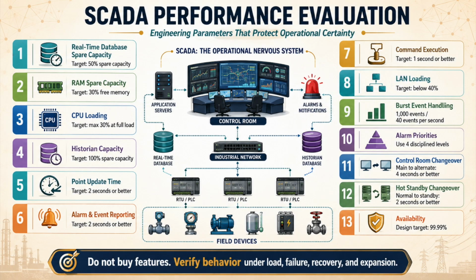The fourth engineering parameter is historian capacity, because the historian is not only a trend database, it is the memory of the asset, supporting maintenance analysis, incident investigation, compliance review, custody review, energy optimization, performance monitoring, root cause analysis, shift handover, and long-term operating knowledge. After an event, nobody asks whether the trend screen looked attractive. They ask whether the event can be reconstructed.